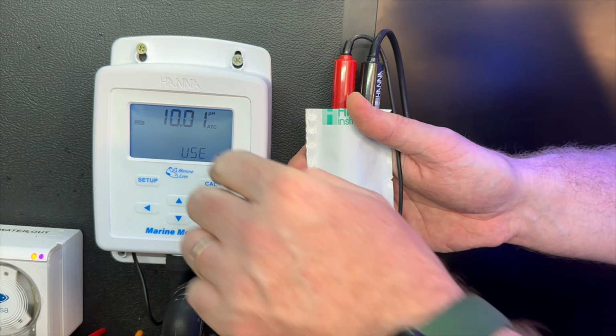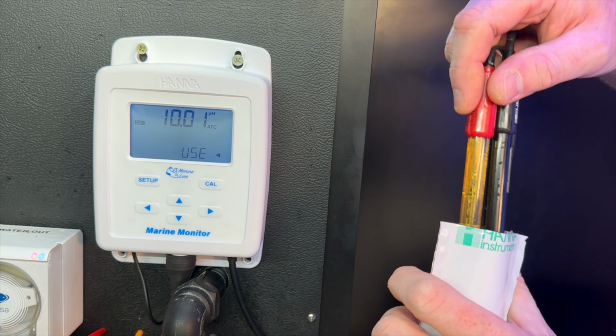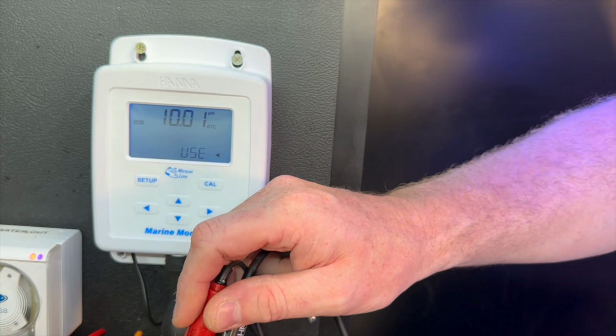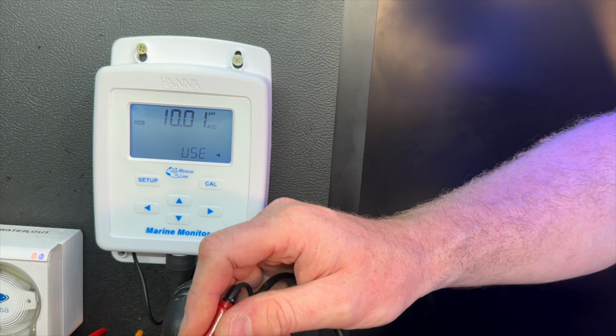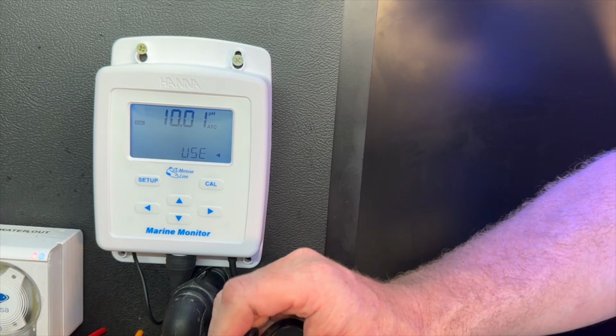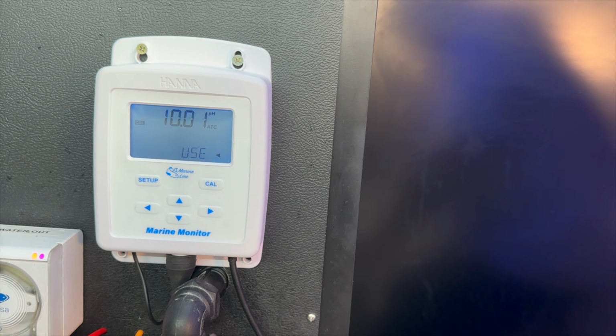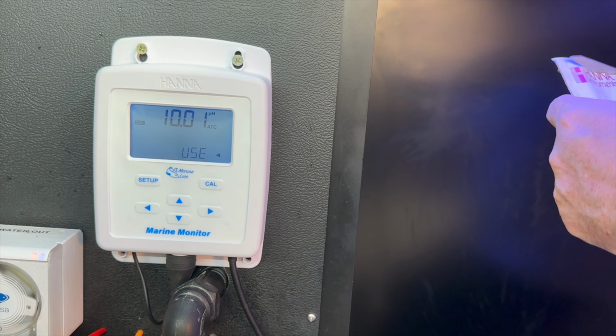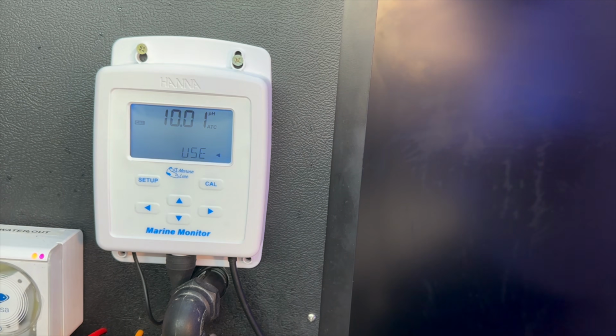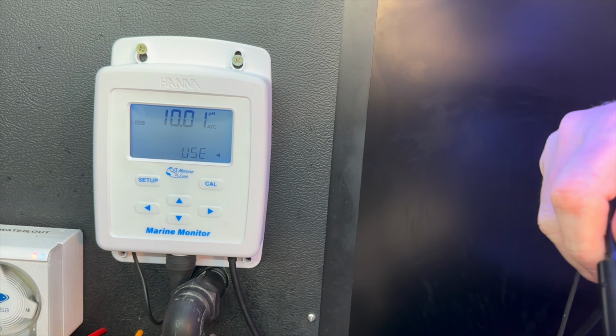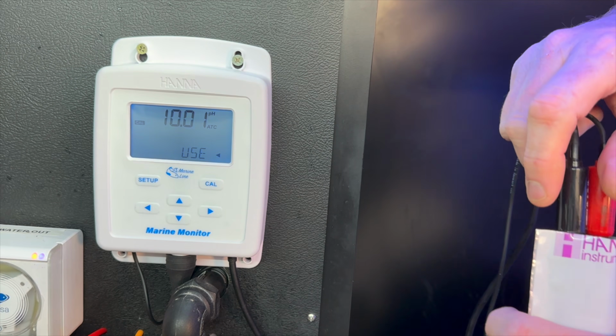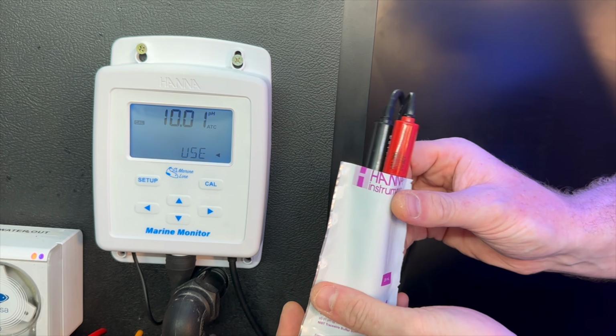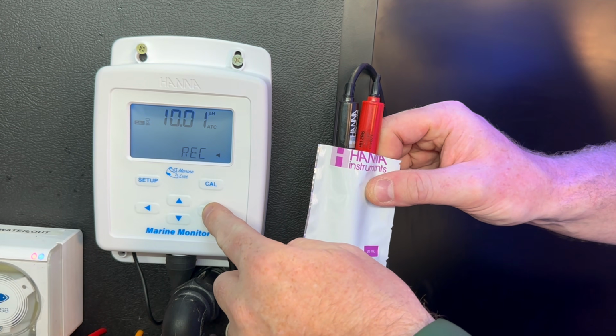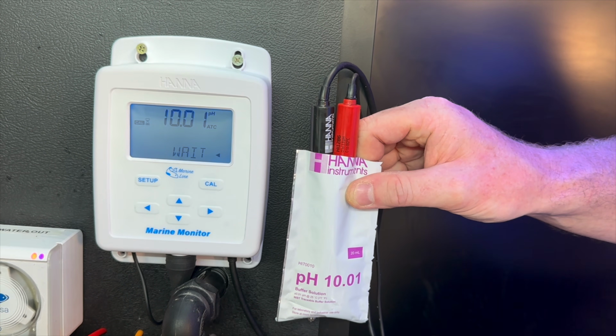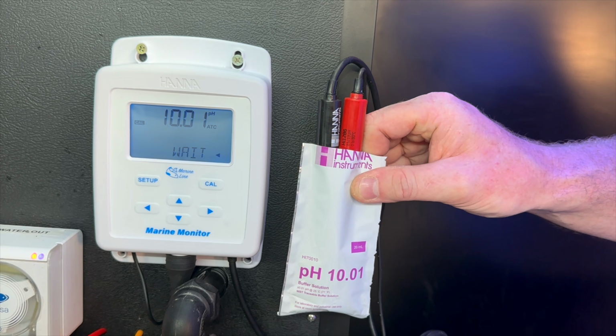Okay, now it's telling me to grab the 10.0 pH, so we're going to take these probes out of the 7.0. Again, we're going to give them a little shake off because we don't want to transfer that 7.0 solution across into the 10.0 fluid. I'm going to grab a 10.0 solution packet here. I'm going to cut the top off him. Now that my probes have been cleaned, I'm going to pop those into the 10.0 solution. Now we're going to say to the right. It's telling us to wait.